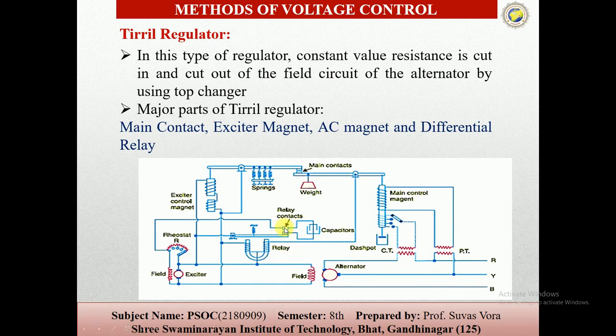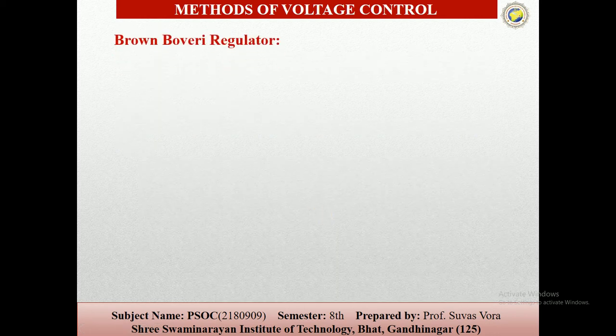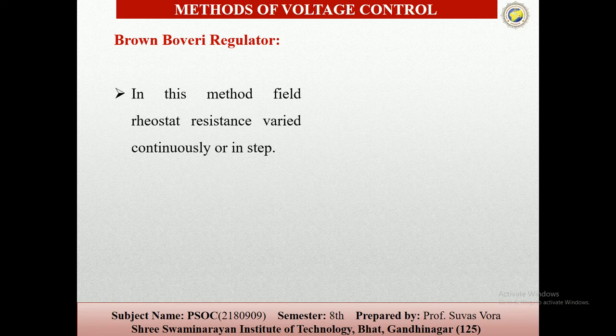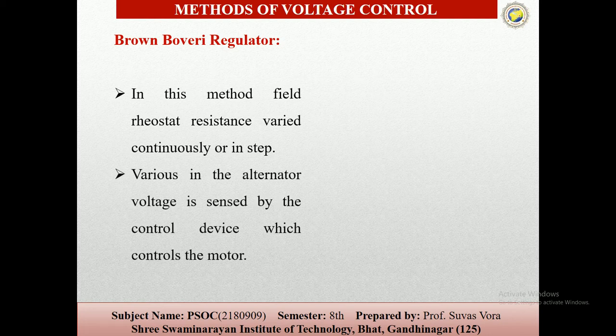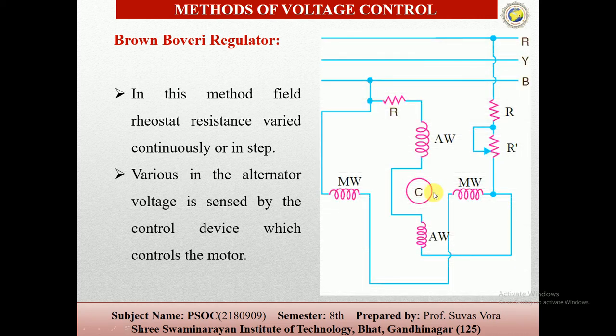Generally the relay contact is open. When a fault arises, the relay will be energized and the relay contact will be closed. To set the rheostat values, at that time this one is released. Then the Brown-Boveri regulators: in this method the field rheostat resistance varies continuously or in steps, and the variation in the alternator voltage is sensed by this control device, which controls the motors. You can see here there are two windings, the main winding and the auxiliary winding. The auxiliary winding is divided into two parts, and we can see the variation in the regulators.